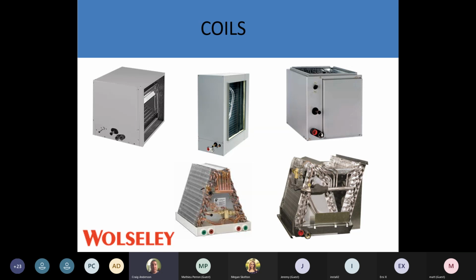So in the case, you'll notice when these come out that it's an A coil, but it's upside down. So it's designed for superior airflow. We're getting better airflow once it's going through the V out of the case. As of right now, they're only going to be offered in a case and not as an add-on like the N coil. So for airflow purposes on older oil furnaces with belted motors, where we're worried about airflow, that coil will be coming out in the near future. But we have a variety of coils now, A coils, N coils, all that stuff.